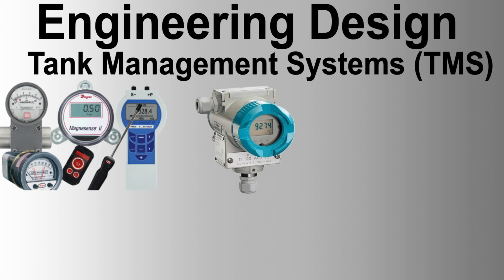7.14.2.1 Objectives. Ensure all deliverable items are present and acceptable. Verify the correct functioning of the TMS software according to the functional specifications. Ensure the system can tolerate failure of individual modules and subsystems and recover to full function following repair. Confirm that all remedial punch list work from the FAT has been satisfactorily completed. 7.14.2.2 Software testing. Retest a random sample of ATG devices to verify TMS-ICS interfacing. Conduct an availability test for a continuous 60-day period to ensure the software meets availability requirements.